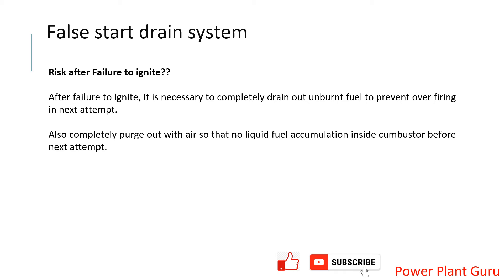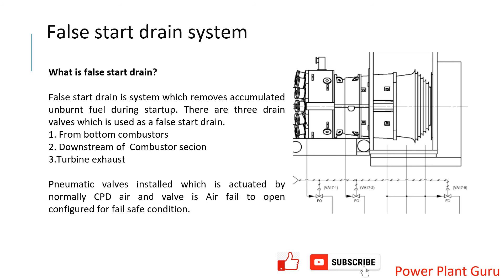If the air is coming, after a few seconds the fuel should also come out, and we should check for that. There is a potential risk of fire and explosion if a lot of fuel has accumulated while we give an attempt to start the machine. If you have done two or three attempts with no stable startup, you will have a lot of fuel accumulated. There have already been different incidents and accidents at power plants where an explosion-type event occurred because of this fuel accumulation.